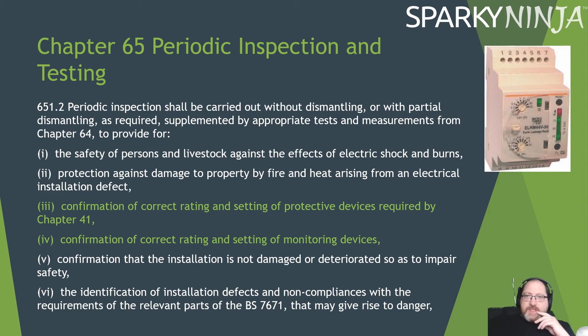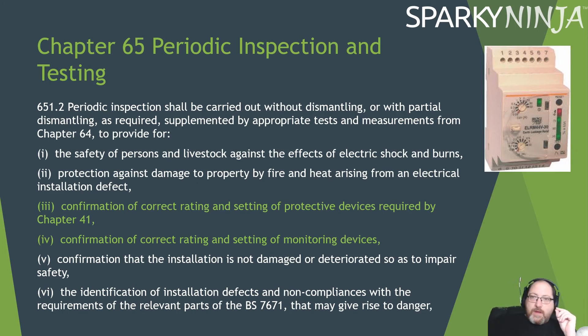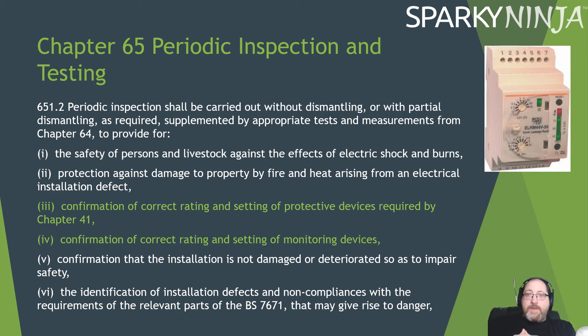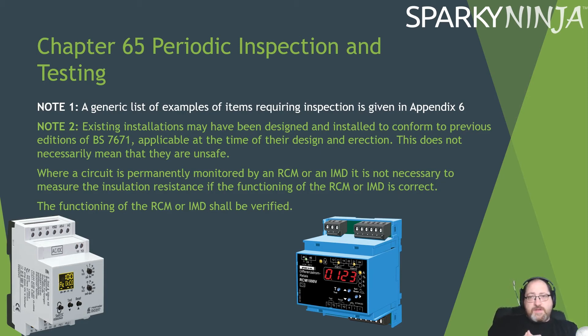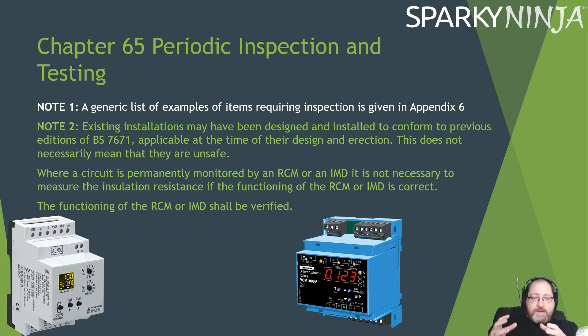Chapter 65, periodic inspection and testing. It shall be carried out without dismantling or with partial dismantling. We verify the safety of persons and livestock, protection against damage to property. But they've also added two things to check: confirming the correct rating and setting of protective devices required by Chapter 41 such as RCDs and selectable RCDs, and confirming the correct rating and setting of monitoring devices. Note 2 states existing installations may have been designed to conform to previous editions — this does not necessarily mean they are unsafe. Where a circuit is permanently monitored by an RCM or an IMD, it is not necessary to measure insulation resistance if the functional verification of the RCM and IMD is confirmed correct.